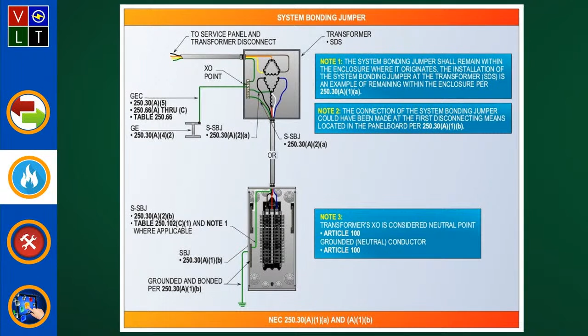And you can go and look in our design book, where we explain this whole layout system and what those notes are about as it relates to that. And then we'll also explain where you need to go in other parts of the illustrations where the calculation would apply, whether you're at the source or the disconnecting means. So if you have a metallic raceway going from your transformer to your panel, then you'd want it at the source. And that source being the transformer, right? That's right. That's why we have one at the transformer and one at the panel board. And if it's PVC, then it's support too. Yeah, support too. No, I'm just kidding.